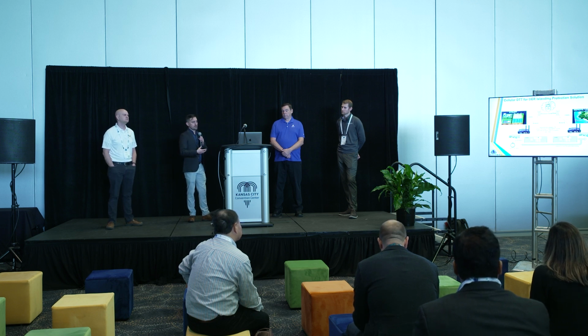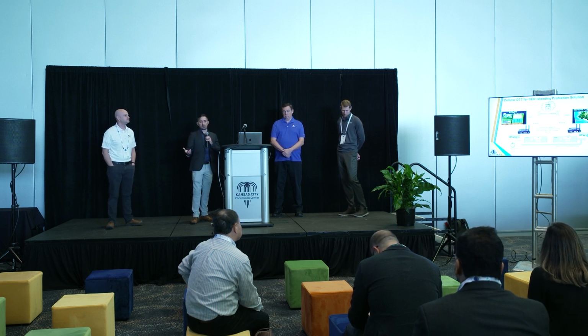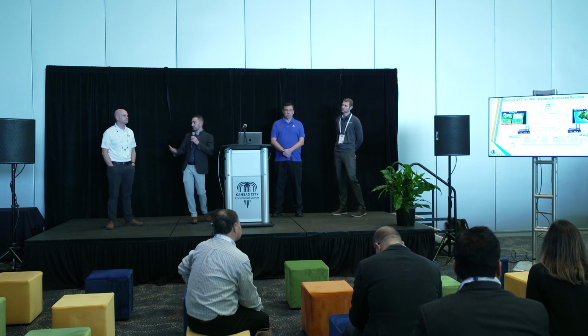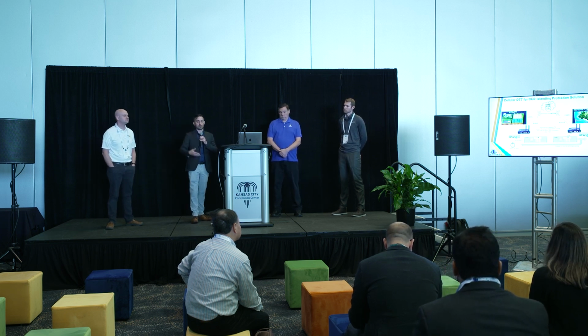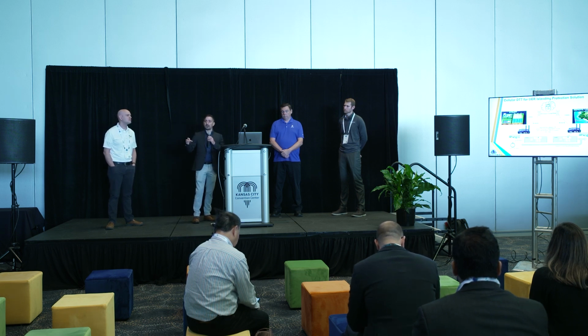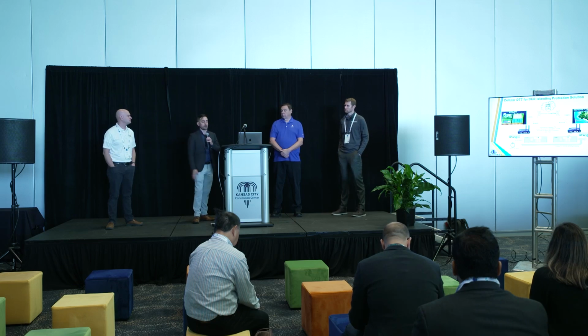Really what we're doing here is active cellular, and we're using a GRE tunnel. The reason you need a GRE tunnel is because cellular typically operates at layer 3, just like the internet, so you're sending things to IP addresses. Unfortunately, GOOSE messaging is a layer 2 protocol. So how do you get that traffic to cross the cellular network? That's where GRE tunnels come into play. We package that layer 2 message into a layer 3 message, send it to the other side, unpackage it, and your layer 2 message just went along for the ride.